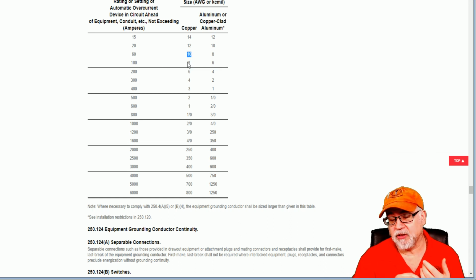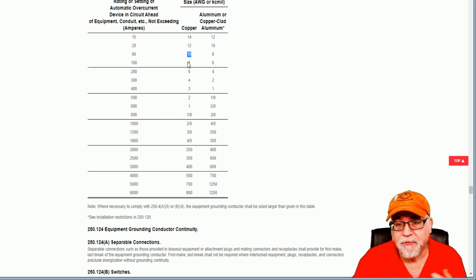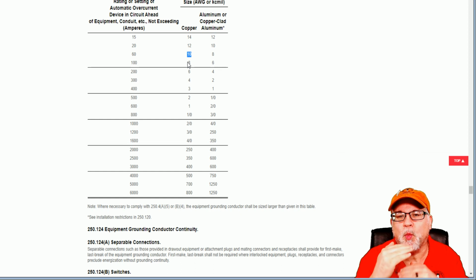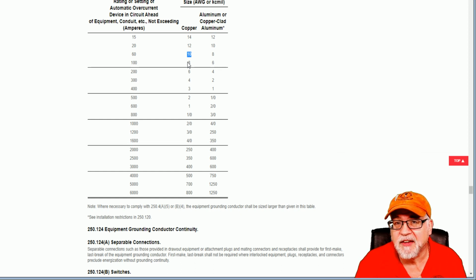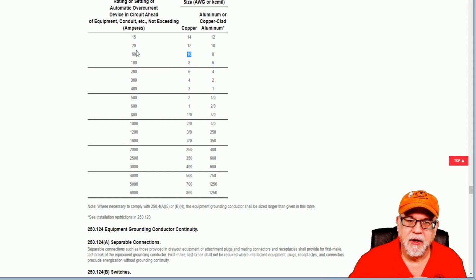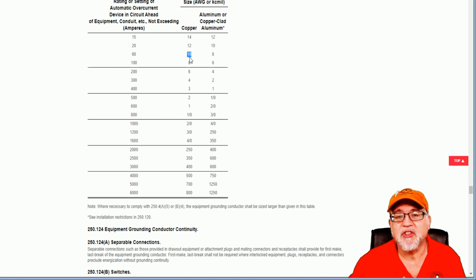Okay? So to answer that question, if it was a 40 amp overcurrent device, 40 amps does not appear here because it falls in that window between 20 and 60. You always jump up to the next size. So in this case, 30, 40, and 50 are all going to fall under the 60, and it's going to be a 10 gauge copper.